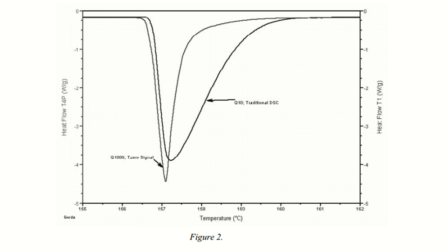Because of this, heat capacity values can be measured in a single run versus the 3 runs required for traditional DSC. This kind of performance results directly from much more complete calibration of the physical components of the system, and use of these calibration values in calculating the heat flow due to just the sample.